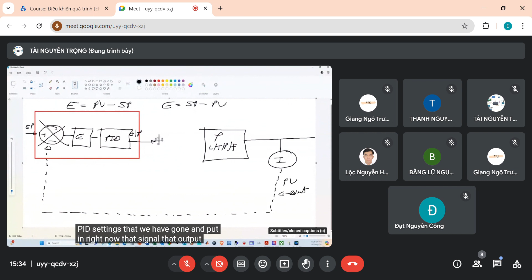The question that was asked was, can we have losses in a closed loop system? Well, if that's going to be a 4 to 20 milliamp signal, what I put in is what I'm going to have out. It's going to go out through the system perfectly. That's probably going to be a 4 to 20 milliamp signal, and that's going to have an influence on my process. The only losses I could have would be physical losses. If I've got a hole in my pipe, or if this tank happens to overflow, and that's only going to be because of bad tuning, then that can come into play itself.